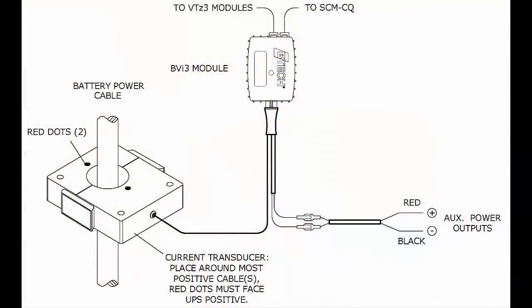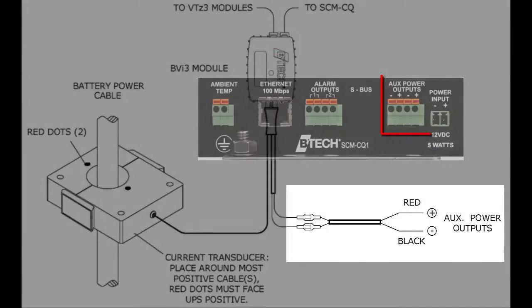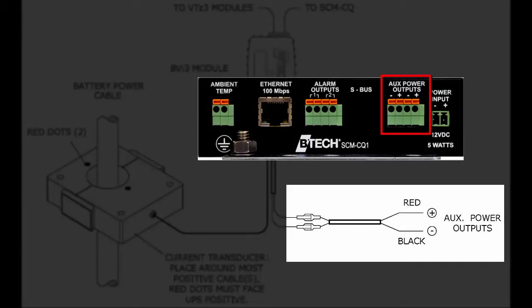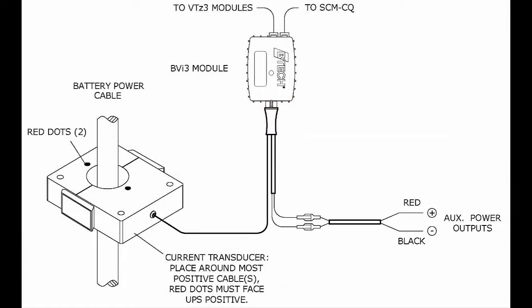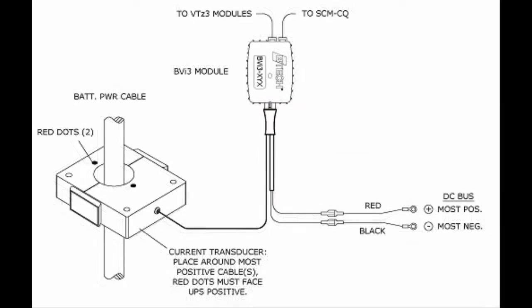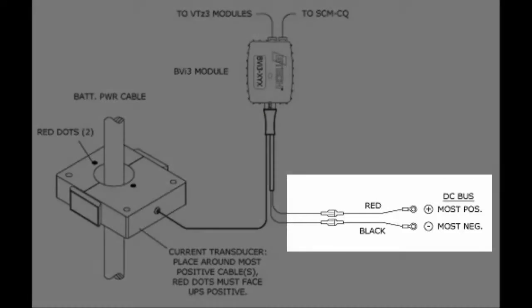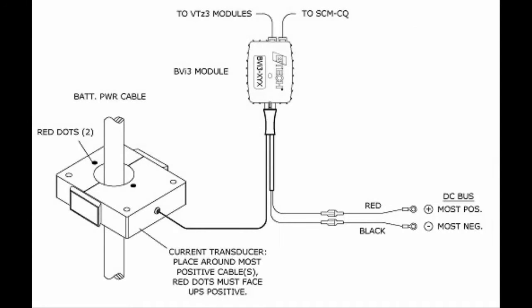If the nominal voltage of the battery string is more than 58 volts DC, the BVI3 must be powered from the CellQ1 auxiliary power output. If the string voltage is lower than 58 volts DC, then the BVI3 is powered from the battery string bus or the most positive plate and most negative plate of the battery string. For more information about the BVI, refer to the CellQ1 manual.